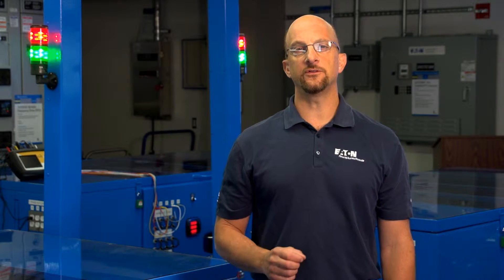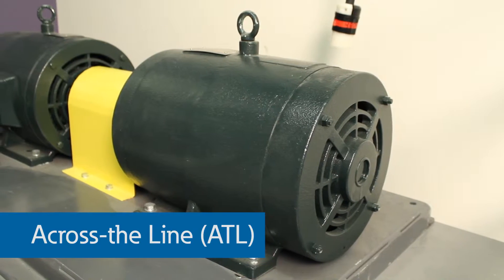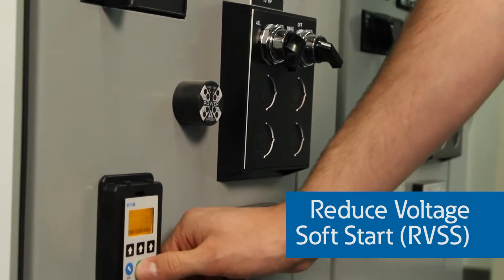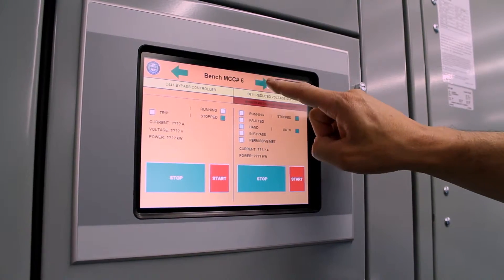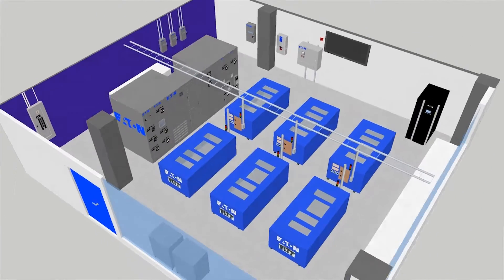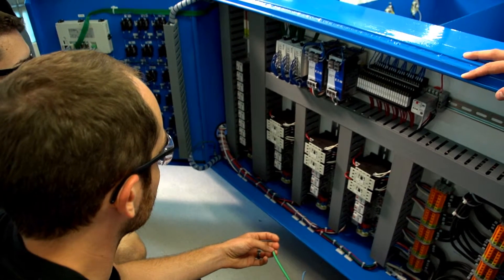In addition, each load bank is configured to connect to a motor control center. Each MCC has the capability to start a 15-horsepower motor either across the line or with a reduced voltage soft starter. Each MCC also feeds a 5-horsepower variable frequency drive, which can generate significant harmonics. The MCCs are fully automated and can be operated with a single touchscreen PLC. The lab benches were designed by students in conjunction with the PSEC staff and departmental technical leads from the University of Pittsburgh. These unique work benches can operate independently or as a group to create power system interaction among loads. Automation and control are featured throughout each of the work benches, showing Eaton's smart wire, contactors, and touchscreen PLCs. Students can configure the PLCs to operate their own bench as well as drives and other automation equipment throughout the lab network.